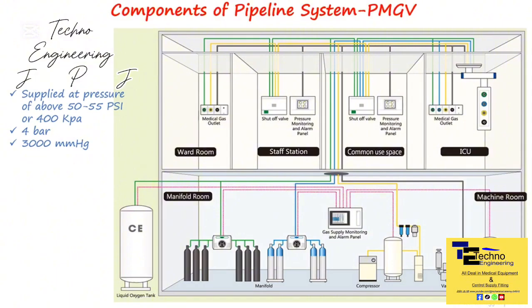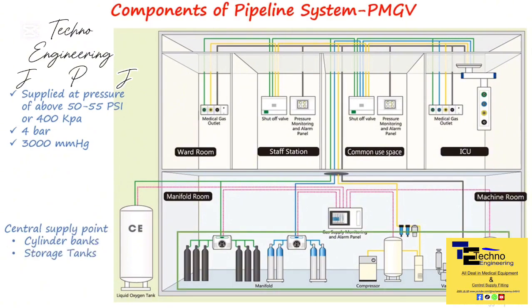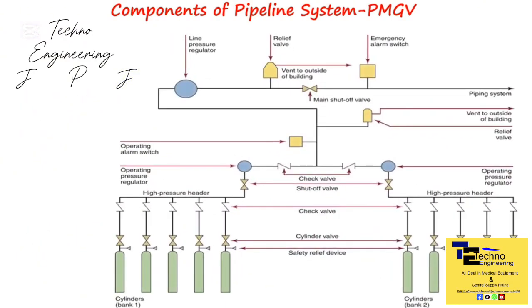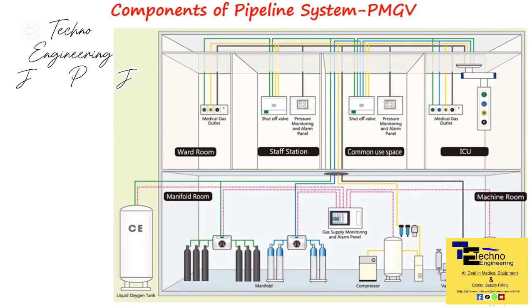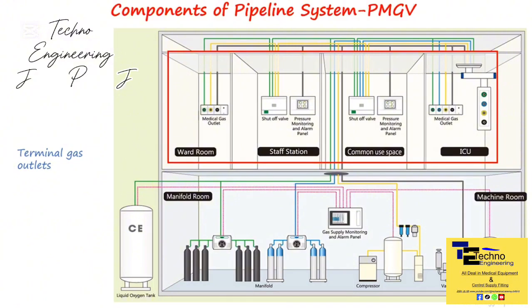Components of the PMGV system include central supply points such as cylinder banks or manifolds, or liquid oxygen storage tanks located separately in a manifold room. Pipelines of varying sizes with their corresponding valves and monitors, pressure regulators and alarms are located throughout the supply system. The terminal gas outlets for final gas delivery are located in the ward, operation theater, ICU, and other facilities.